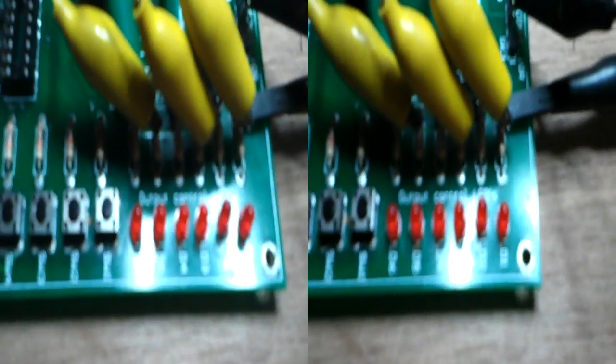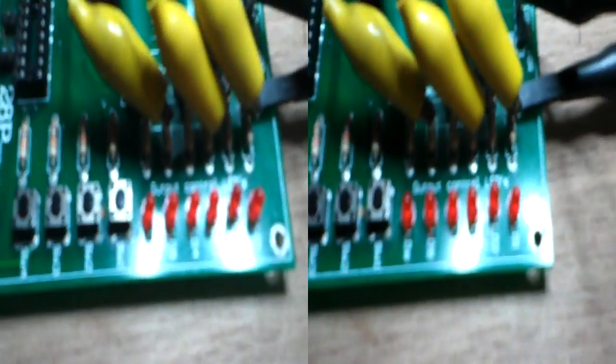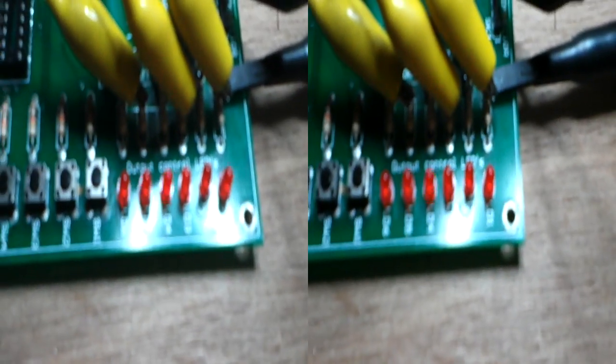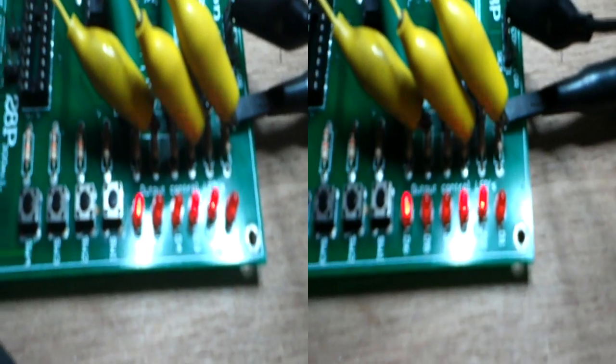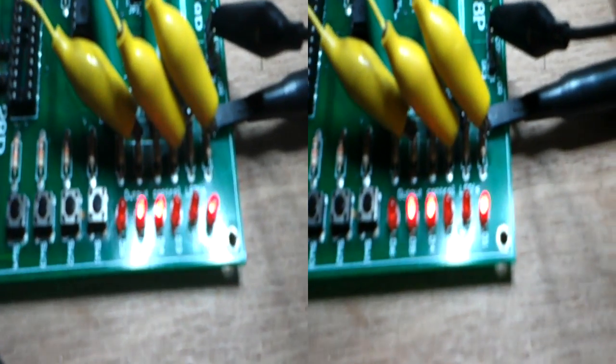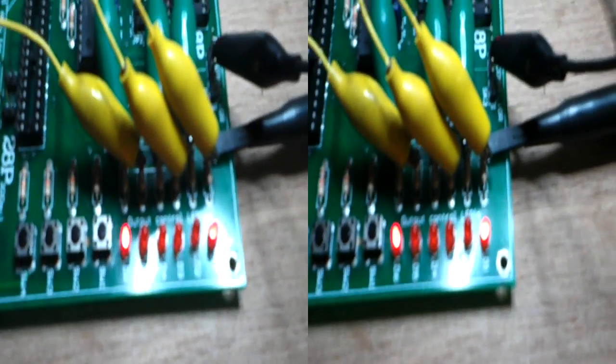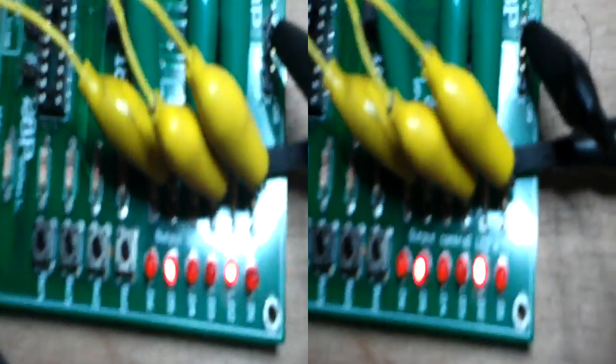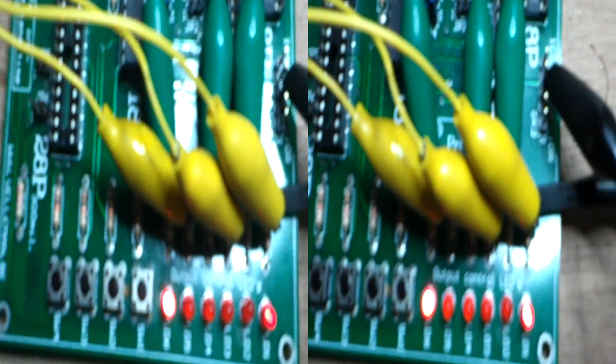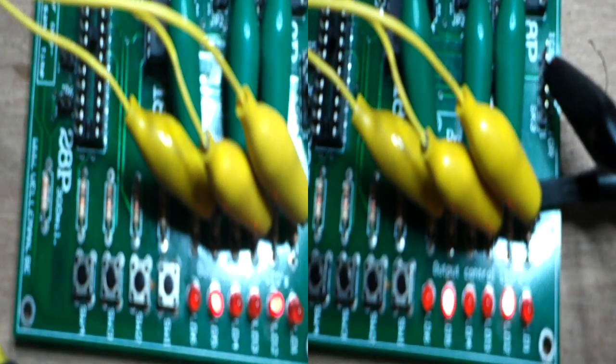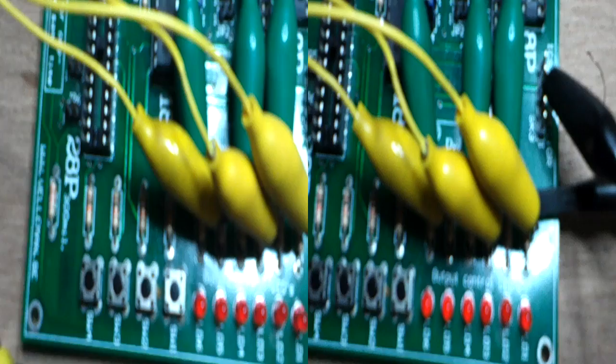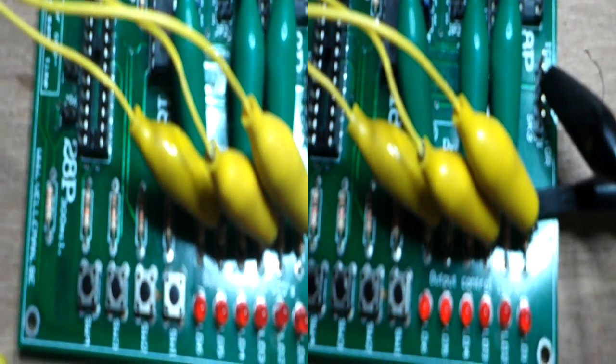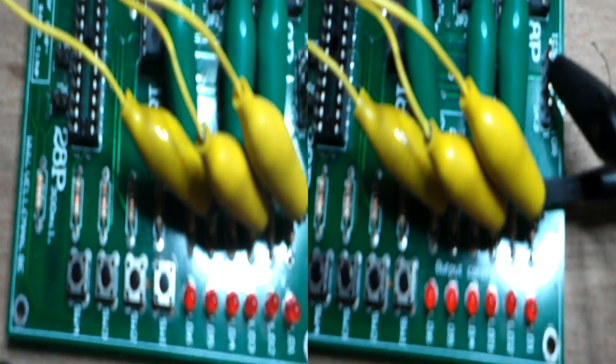And so you can see, if you look at the far right LED, that's the A phase high. And so when that flashes, every time that flashes once, a repeated flash, that's one rotation. So that's one, two, three, four.